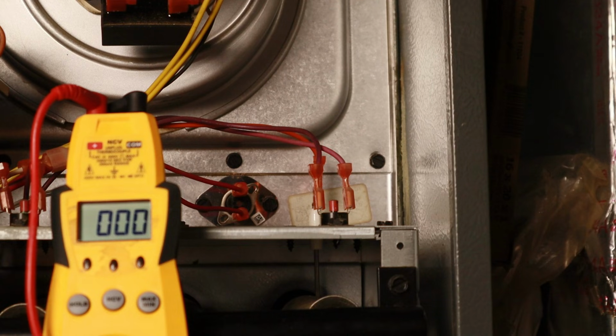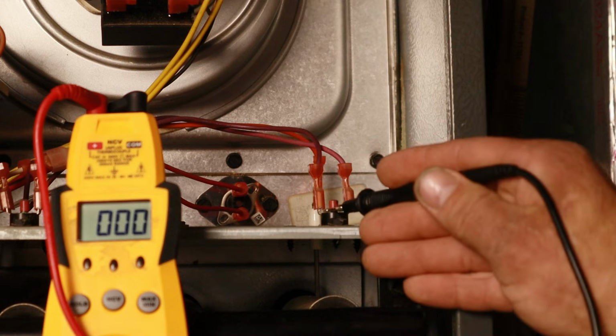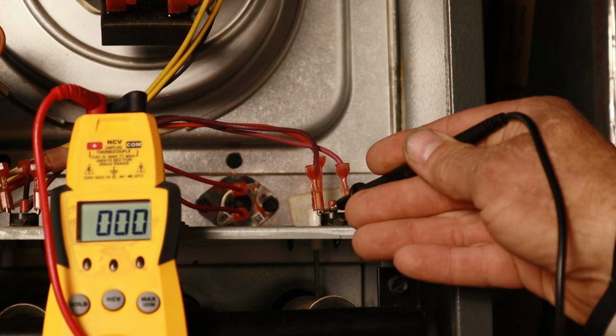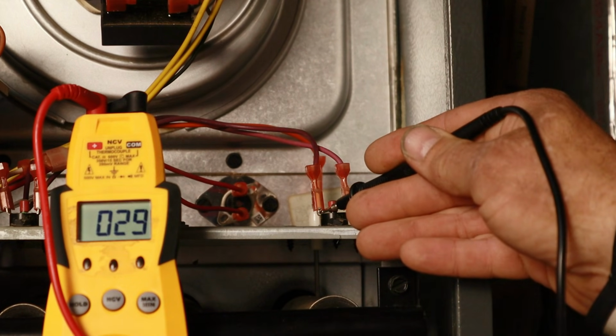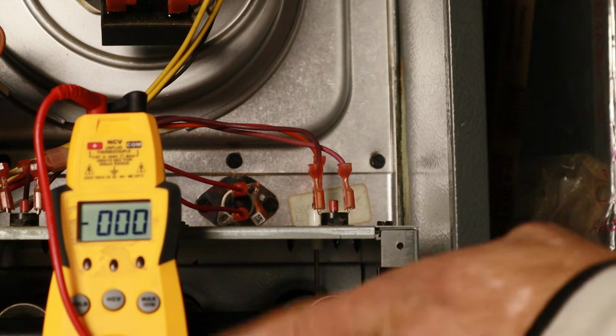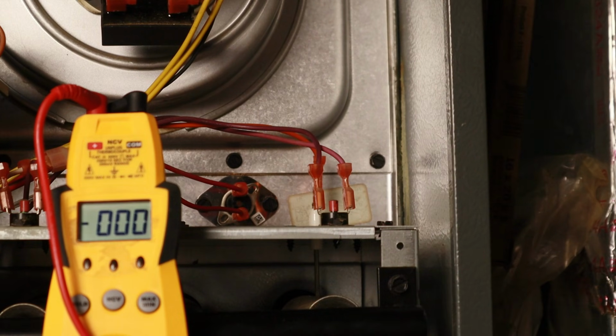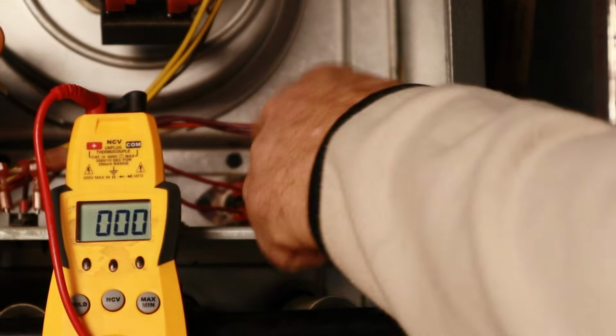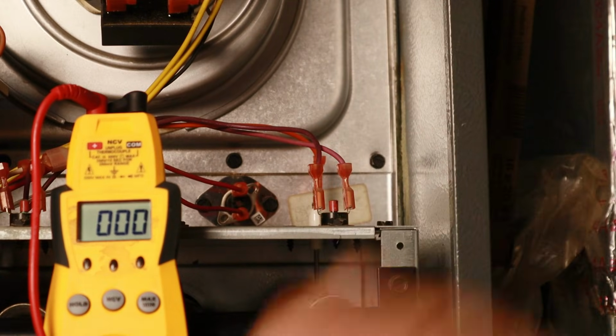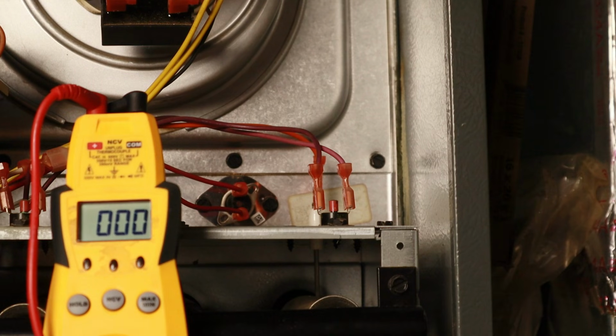So just to show you what I mean, if I were to test for 24 volts right now on this flame rollout, you can see I'm reading 29 volts there. So on this particular furnace, that 24 volts goes through the flame rollouts before it makes it to the R terminal. Now on other units, you might have something different. It might go through that main high limit switch there rather than the flame rollouts. But either way, you can usually test one of those switches to see if you have any power there, and that will tell you that it's worked into the circuit prior to that R terminal.